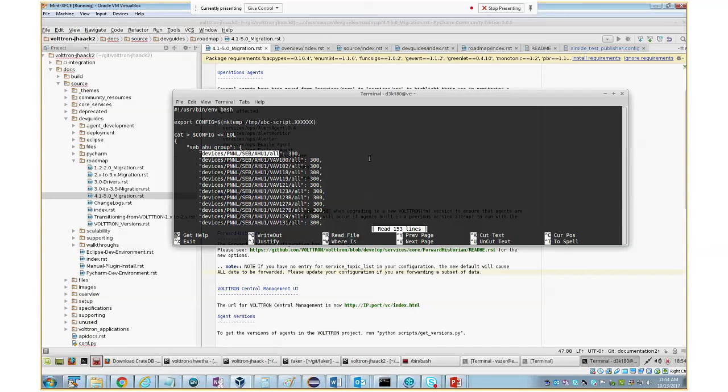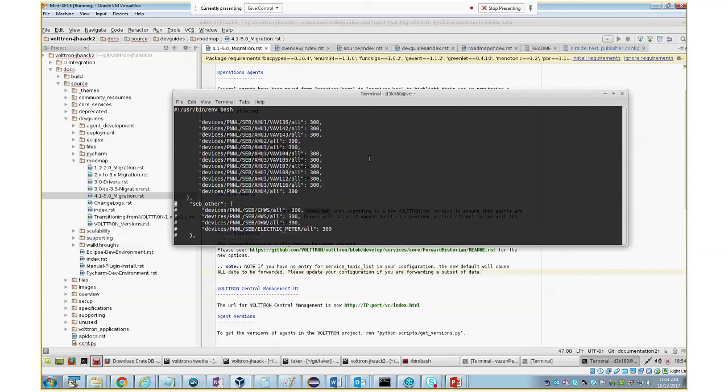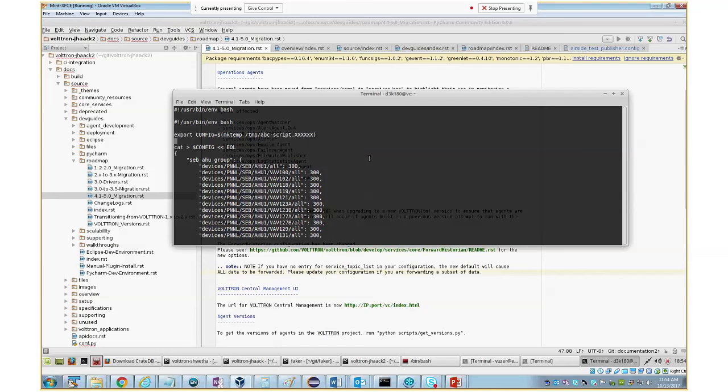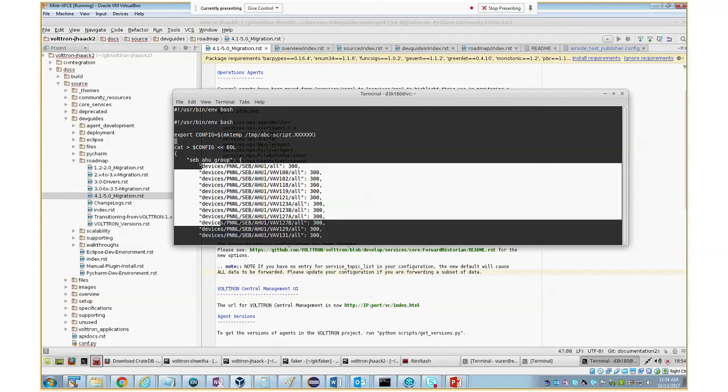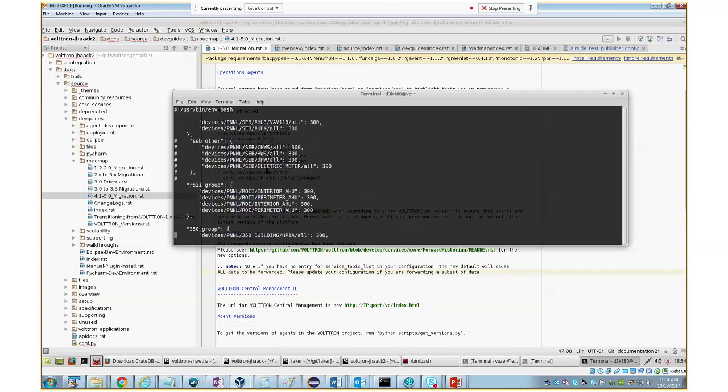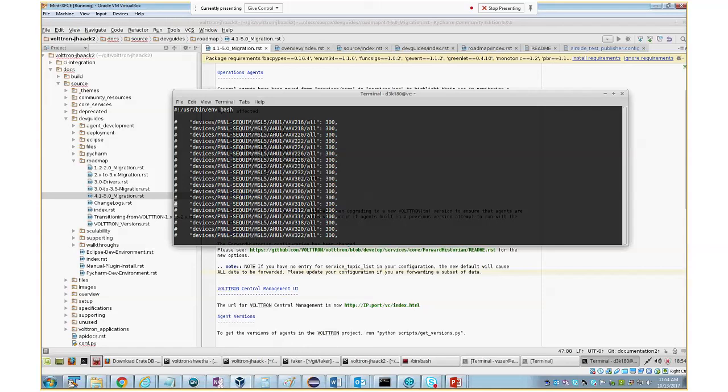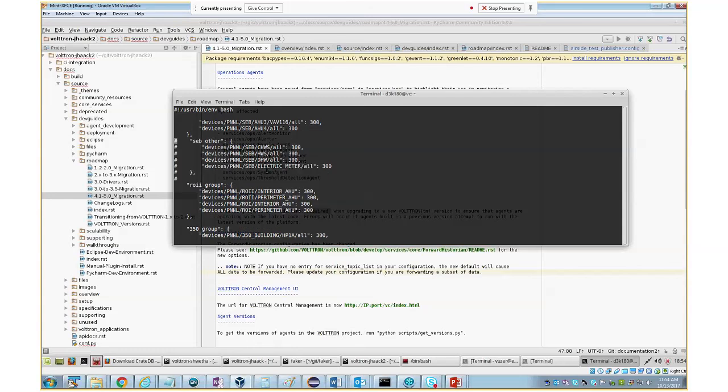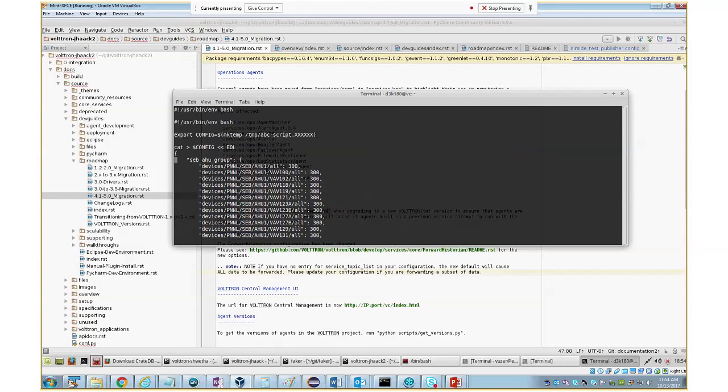So that's a group for that one building. Oh, so we don't get individual alerts for each AHU. Otherwise, we'd get individual alerts for each of these topics if they weren't grouped. If we lose communication to that building, we don't want to get spammed. Okay, I wasn't aware of the grouping thing. It's kind of new. If you have multiple things fail in that group, you get one message. Okay, that makes sense. So that's what a configuration file looks like.